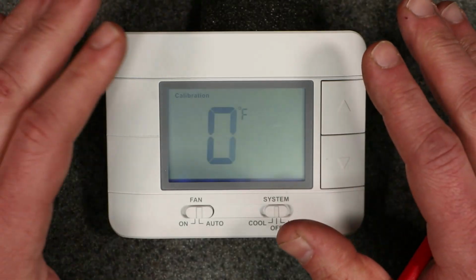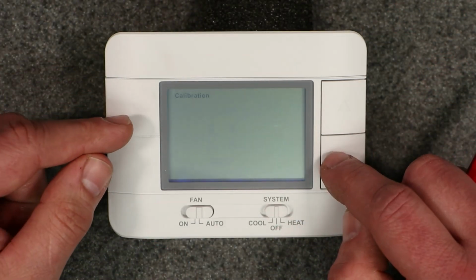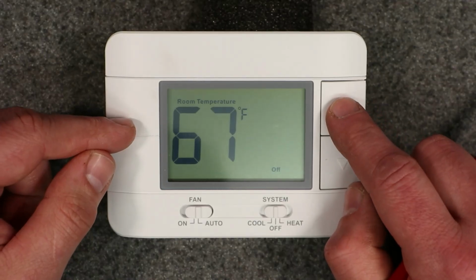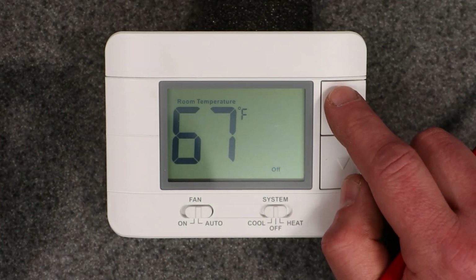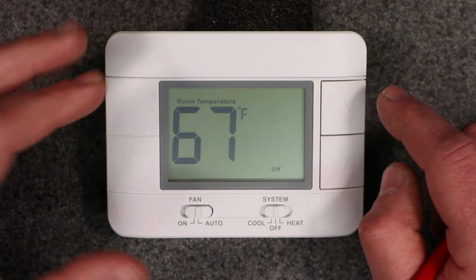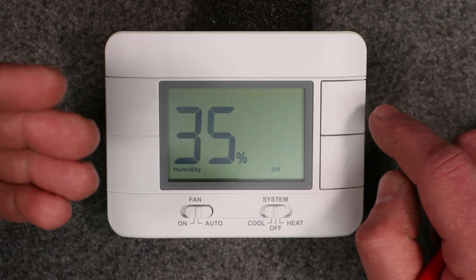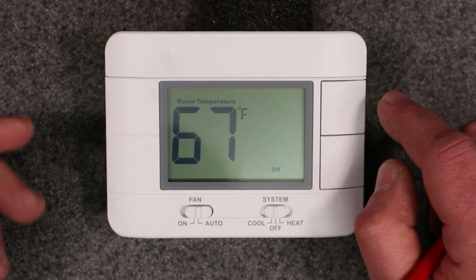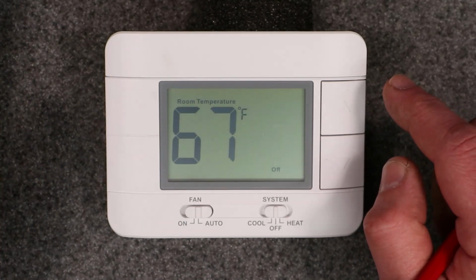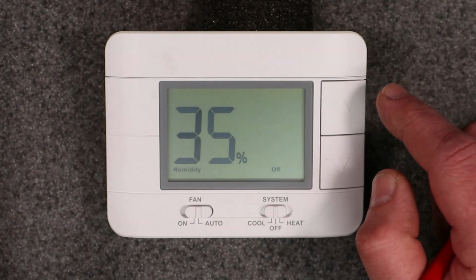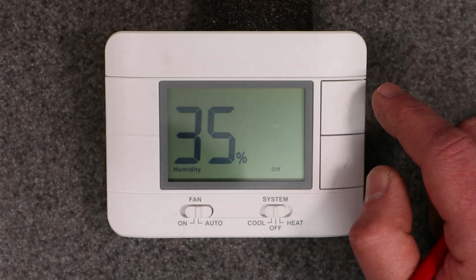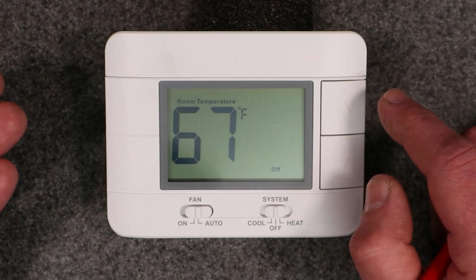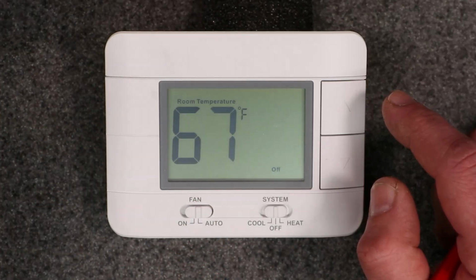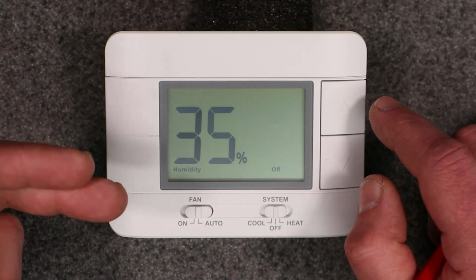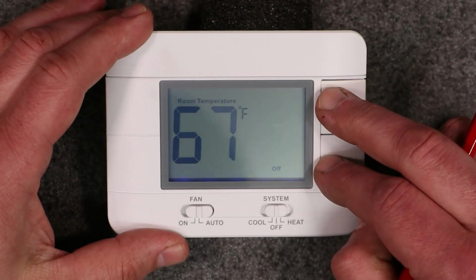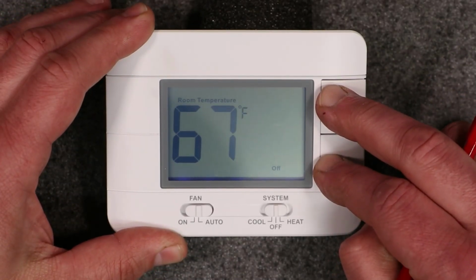This is basically an offset from the nominal temperature. So say you had this set up in a room that's really sunny, you'd want to offset it in the negative, because it's going to get hit with the sun and heat up more than you desire. Or if you want the opposite effect, you'd go into the positive range. This lets you shift around that nominal set point. So if it gets a lot of sunshine, or a lot of cooling from a draft—say a cold draft blowing on the thermostat, like if it's in a garage—you'd want to offset that, positive or negative. So it gives you that option.